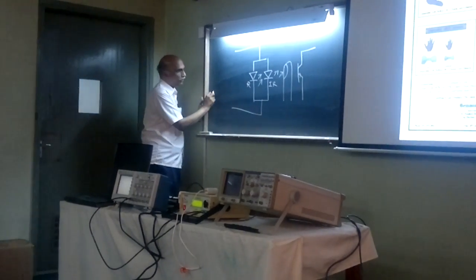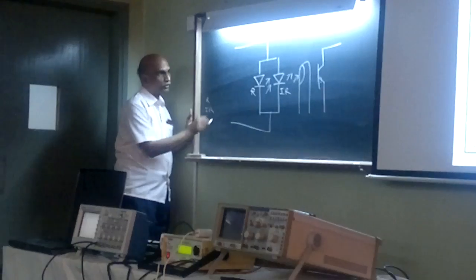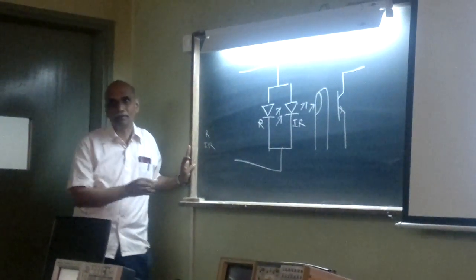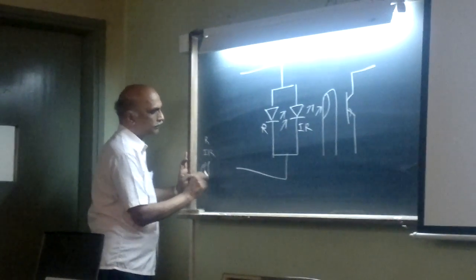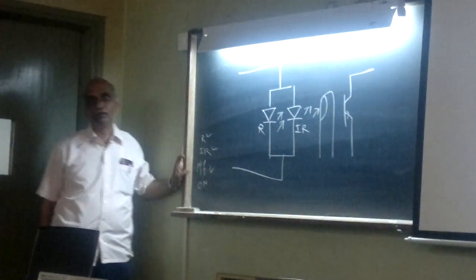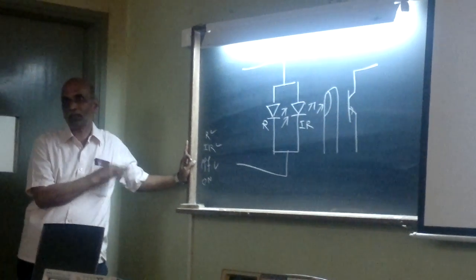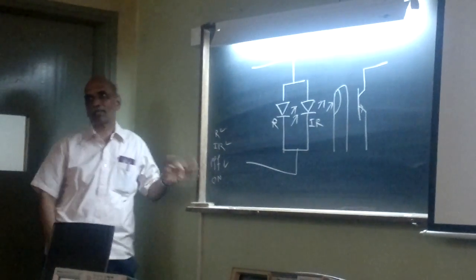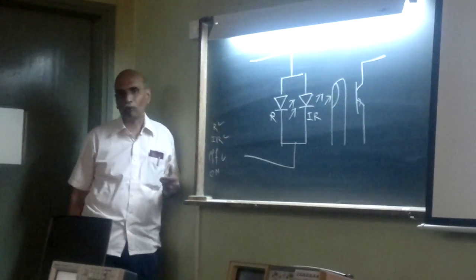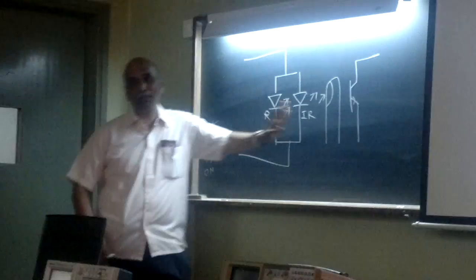Now, either you must have red on or infrared on. You can have both of them off. That is possible. This is acceptable. But both of them on is not possible. You cannot put both together at the same time. Either you must have red or infrared or both of them off. Now, when both of them are off, the detector sees the ambient light.